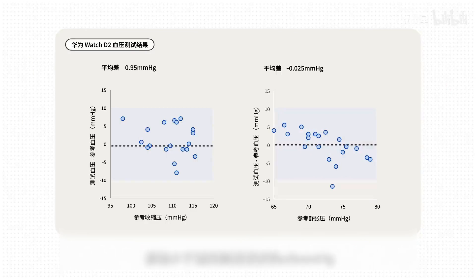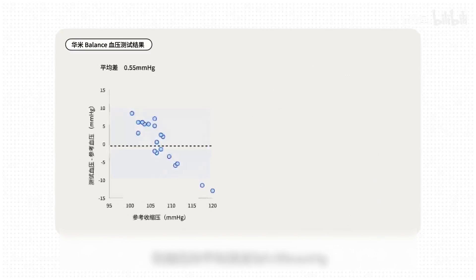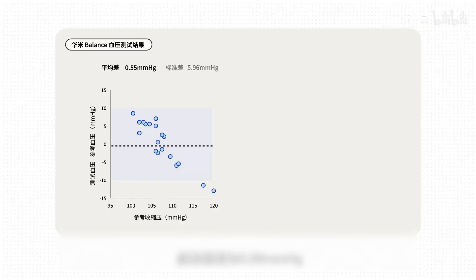It's still very accurate, which is much smaller than the ±5 mmHg required by the general standard. The standard deviation of systolic pressure is 4.2 mmHg and the diastolic pressure is 4.30 mmHg, also meeting the general standard requirement that standard deviation is less than 8 mmHg. The error distribution of the entire scatter plot is also relatively uniform. Looking at the Huami Balance that uses PPG measurement: the average error of systolic pressure is 0.55 mmHg and the standard deviation is 5.96 mmHg — also meeting the requirements of the general standard, but the standard deviation is slightly larger. The scatter plot also shows Huami has a kind of regular trend of overestimating low blood pressure and underestimating high blood pressure.